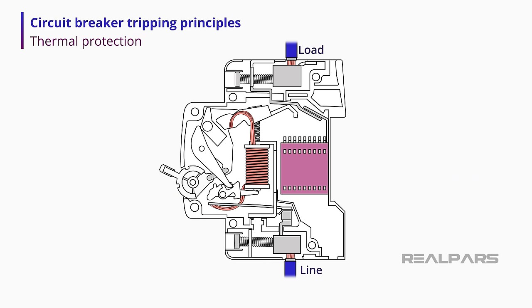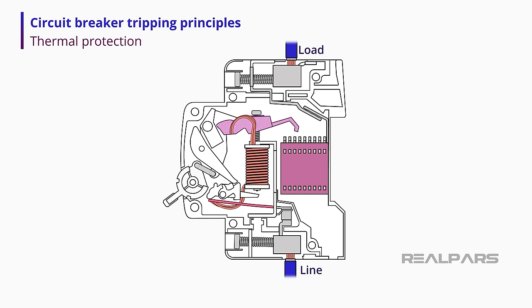Looking at thermal protection, the bimetallic strip heats up with the current. If the circuit's current rises over a certain level, the strip will bend, moving the switch linkage, and consequently the moving contact, breaking its connection to the stationary contact, causing the circuit to break.